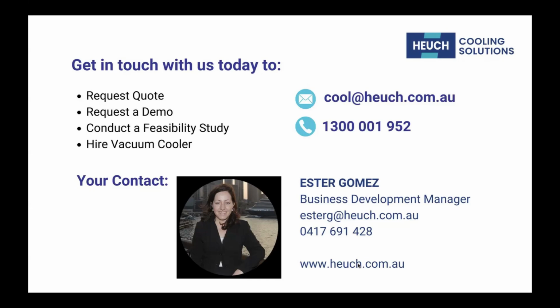On the one hand, you have a very fast cooling time for bread. It's really minutes, 5 or 6 minutes. And then you need to shorten your baking time. For thin bread, it can be around 30% on average. So it's not only about fast cooling, it's about saving a lot of time in the oven. That's one of the main benefits of vacuum cooling for the bakery, particularly at scale. If you have 5 ovens operating at, let's say, 60 minutes per cycle, and that's 6 cycles per day, and you reduce every one of those by 30%, you can save literally hours of production time per day, just in baking time, putting cooling aside.